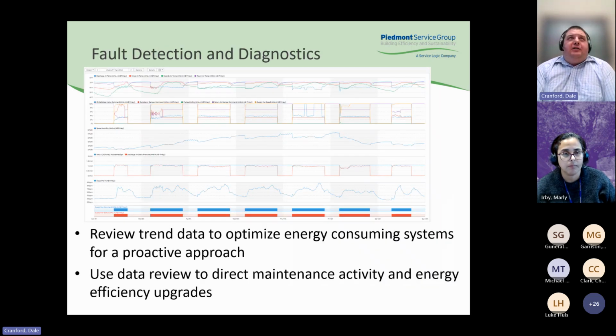Another thing that has come out in recent years that's really helping on the control side is using analytics for fault detection and diagnostics. So you can review the trend data from your BAS with multiple variables at one time to optimize your energy consuming systems for a more proactive approach. So you can look at different variables that can tell you things that a normal building automation system alarm may not tell you. A typical alarm is just going to tell you if a system's down and it's not operating, or maybe one parameter is out of the tolerance that it should be.